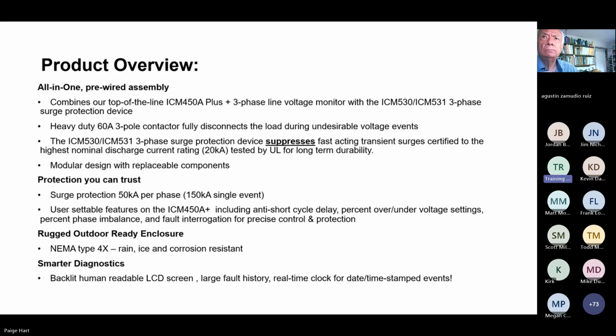This provides you protection that you can trust. You got a very good surge protective device that's protecting 50,000 amps per phase, or 50 kiloamps per phase, same thing, 50,000 amps per phase for a maximum of a single event of 150,000 amps.